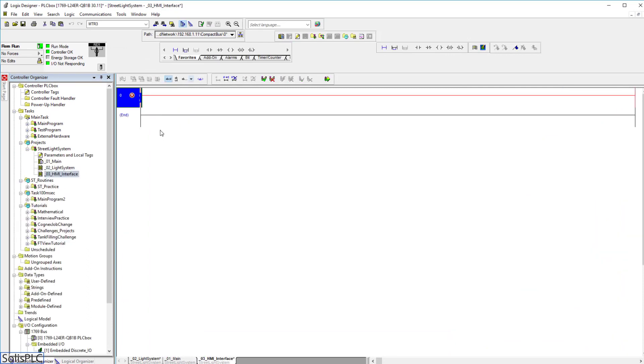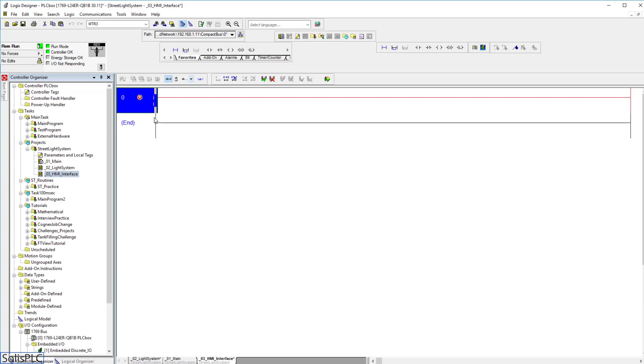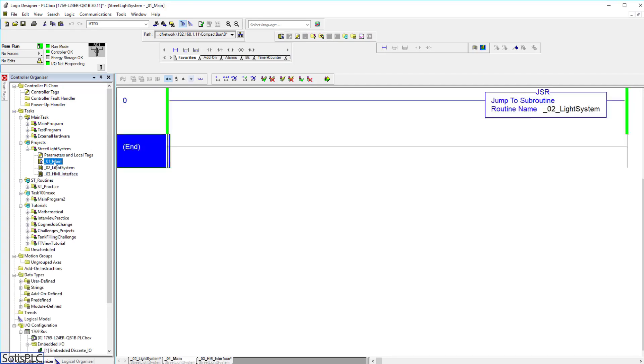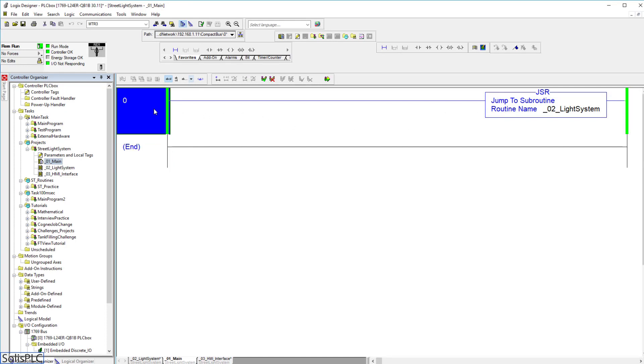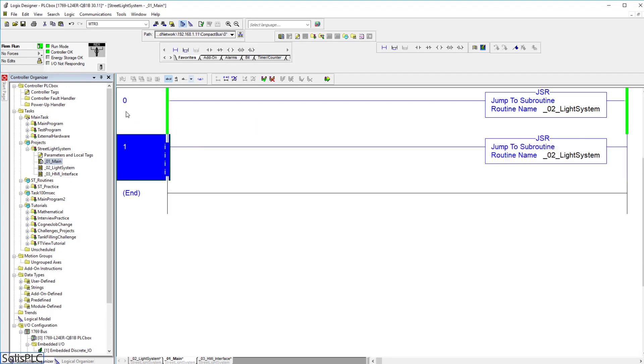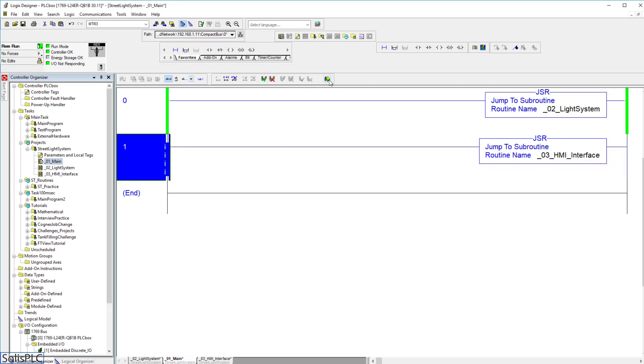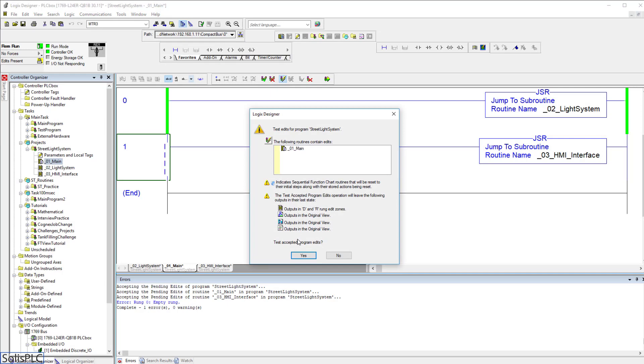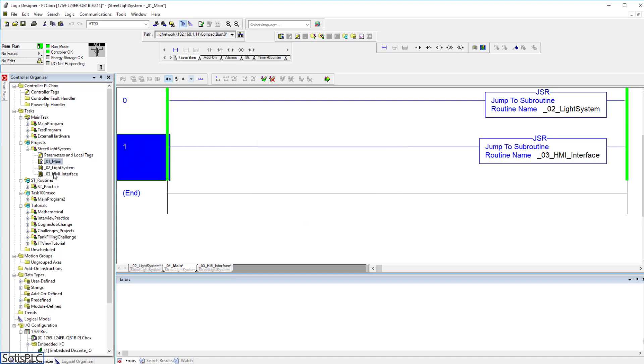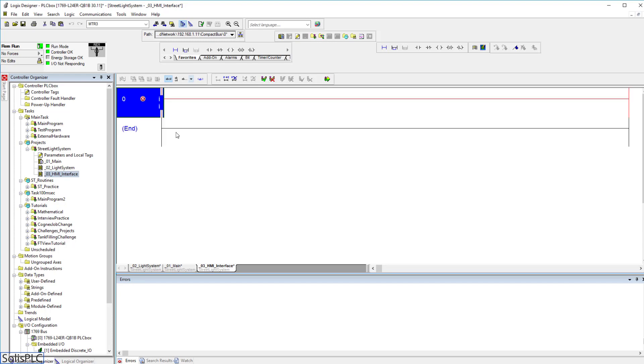Once I double-click this interface, you'll notice the left area is not green, because we need to go back into the main. Double-click the main, and we need to implement the same jump-to-subroutine that we've done before. I'm going to copy and paste this rung — you can use Ctrl+C and Ctrl+V or right-click and copy — and call it 03_HMI_interface. Instead of assembling the entire routine right away, I'm going to hit accept pending program edits, then assemble accepted. As you can see, we are now jumping into this HMI interface, so this interface should now be enabled.